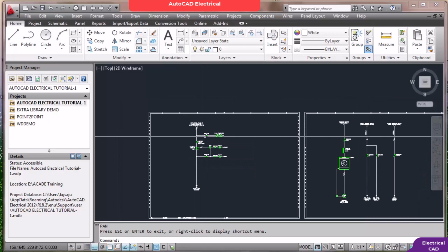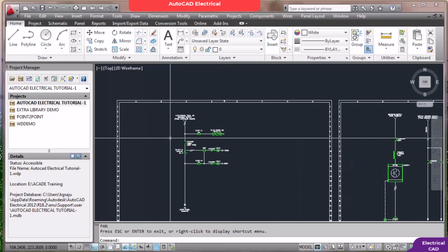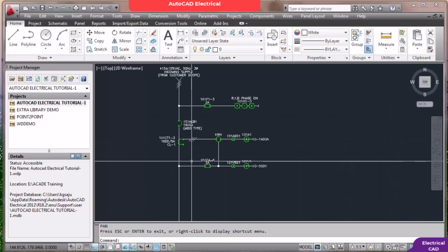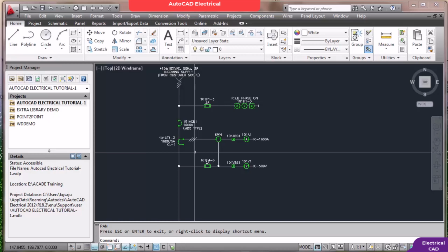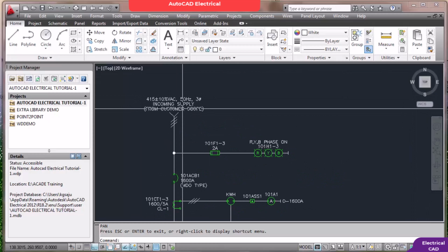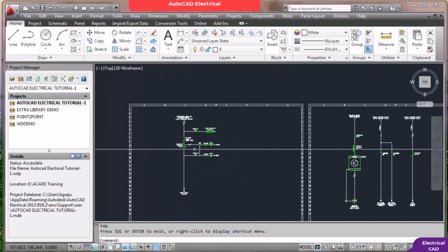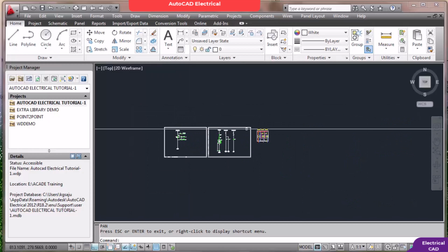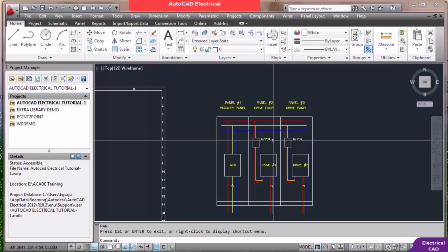That's all. In many cases, when you get a project, you may not get sufficient time to prepare a detailed wiring diagram. So what people normally do is prepare a proposed power distribution scheme, which you can call a single line diagram. This is how it looks. We will take your supply from the customer side and connect it through the ACB, and the rating will be this, and it will be connected like this. This is a single line diagram. Simultaneously, I also prepare a panel layout, with the exact dimensions and all, and it will look like this.